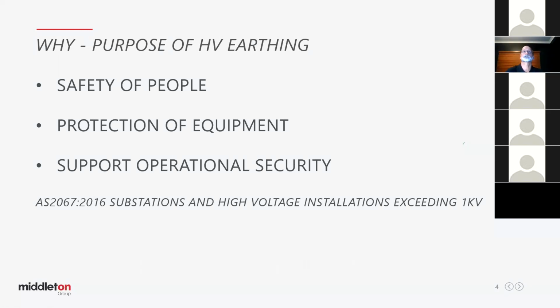So as we asked earlier, what's the purpose of HV earthing? Well, quite obviously for safety of people. But secondly, for protection of the equipment. The earthing ensures that the fault current flows, so the protection picks up the fault and allows the circuit to be tripped. So we're protecting the equipment. If we don't, obviously all that energy is going to be dissipated in the equipment for a long period of time and potentially damage that equipment, or it'll catch on fire, burn to the ground.